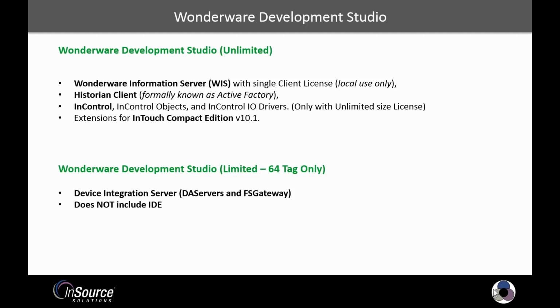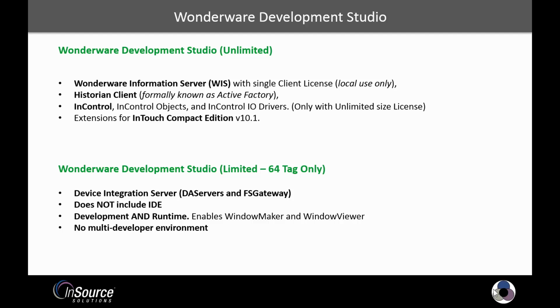If we have a customer that says, I have an InTouch application that will only have 50 tags, what type of license would you have for me? This Development Studio Limited would be that license. They can develop with that license, as well as use that same license for runtime. The exception here is we cannot use it to develop a Galaxy-based application. It's only meant for small InTouch Modern or standalone applications. And because of that, it does not enable a multi-developer environment.